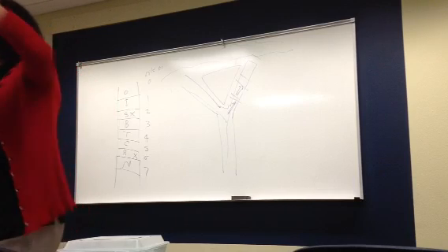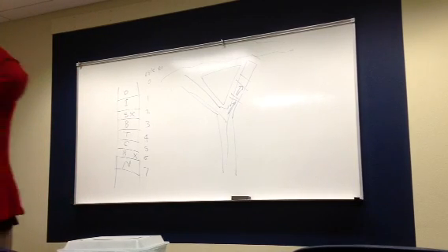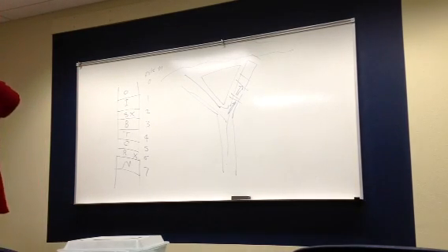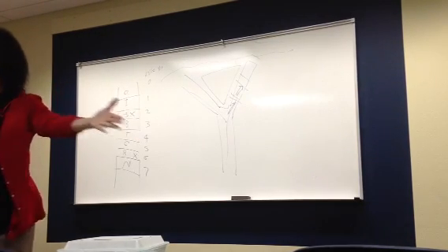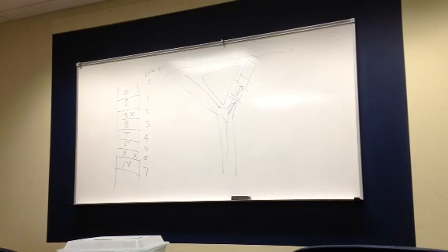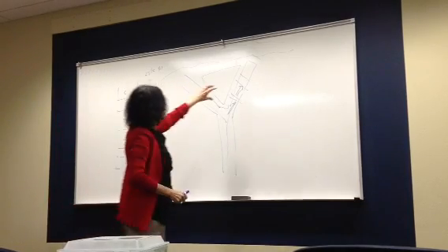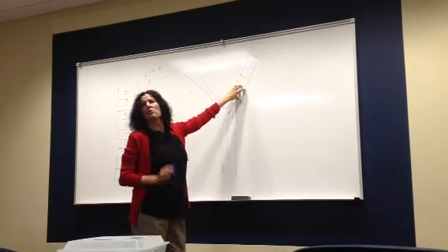When it's a huge river like that, and you want to really do big control like that, as an instrumentation engineer, if you're doing the control, other people doing the instrumentation, no, it's not a swimming pool. For example, the east to west pump station was okay with one downstream, because it was like a swimming pool. But here, no, I said I want 3 transmitters.